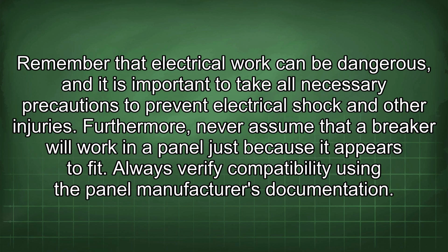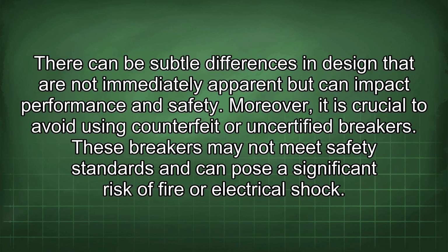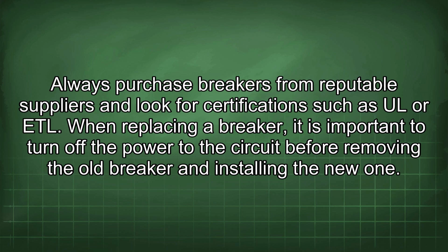Furthermore, never assume that a breaker will work in a panel just because it appears to fit. Always verify compatibility using the panel manufacturer's documentation. There can be subtle differences in design that are not immediately apparent but can impact performance and safety. Moreover, it is crucial to avoid using counterfeit or uncertified breakers. These breakers may not meet safety standards and can pose a significant risk of fire or electrical shock. Always purchase breakers from reputable suppliers and look for certifications such as UL or ETL.